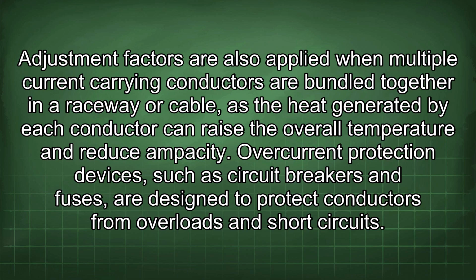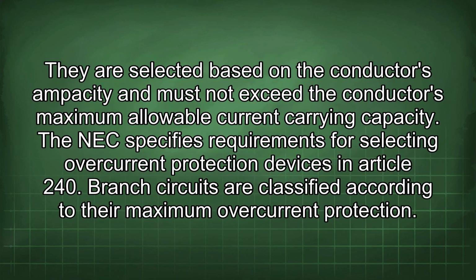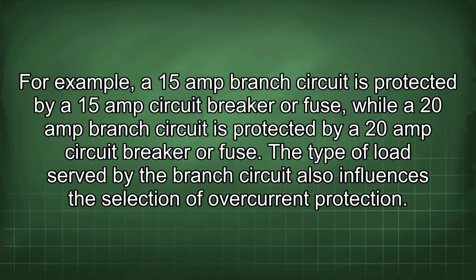Overcurrent protection devices, such as circuit breakers and fuses, are designed to protect conductors from overloads and short circuits. They are selected based on the conductor's ampacity and must not exceed the conductor's maximum allowable current carrying capacity. The NEC specifies requirements for selecting overcurrent protection devices in Article 240. Branch circuits are classified according to their maximum overcurrent protection. For example, a 15 amp branch circuit is protected by a 15 amp circuit breaker or fuse, while a 20 amp branch circuit is protected by a 20 amp circuit breaker or fuse.